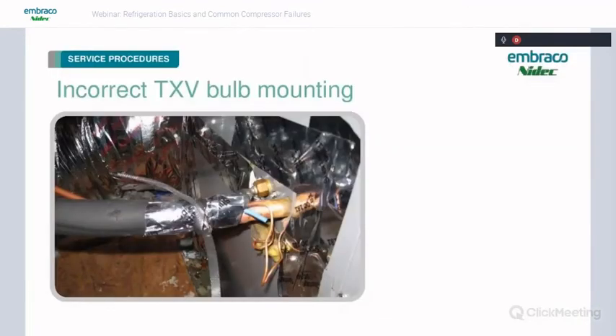And here's an example of someone who did not use the correct clamp. I'm hoping he lost the clamp and he just made do with what he could, and he's coming back tomorrow to put that clamp on and fix it all up. But this is going to cause problems. It's going to loosen up over time if it's not already loose. It's not going to get a good reading of that suction line, and it doesn't look insulated well. So that means ambient temperature is going to affect that bulb. It's going to tell that bulb that the suction line is warmer than it really is, which is going to cause the TXV valve to open wide open.